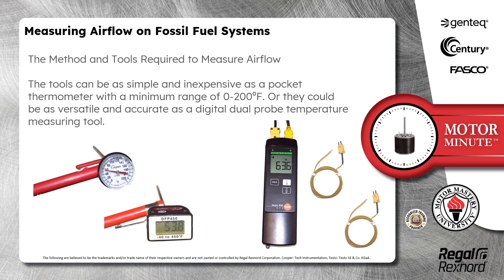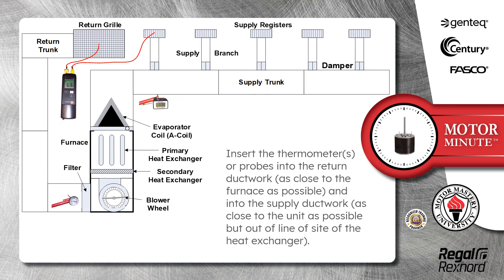The tools can be as simple and inexpensive as a pocket thermometer with a minimum range of 0 to 200 degrees Fahrenheit, or they could be as versatile and accurate as a digital dual probe temperature measuring tool. Insert the thermometers or probes into the return ductwork as close to the furnace as possible, and into the supply ductwork as close to the unit as possible, but out of line of sight of the heat exchanger.